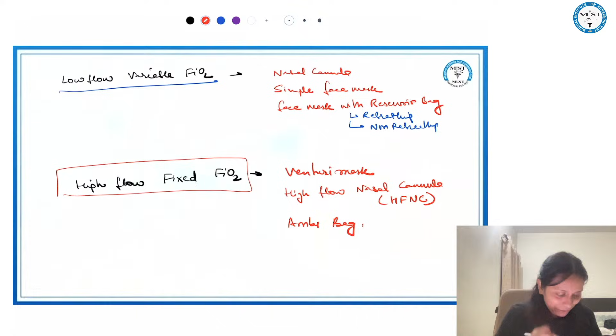Now, about this ambu bag, I want to add something. It can be used not only for oxygenation, but also for ventilation, mechanical ventilation. So I always say the ambu bag is your handheld ventilator. And an ambu bag can give oxygen concentration from 21%, that is room air, to 100% if we have a source of oxygen attached to it. High flow fixed FiO2 delivering device. Got my point? Understood this?